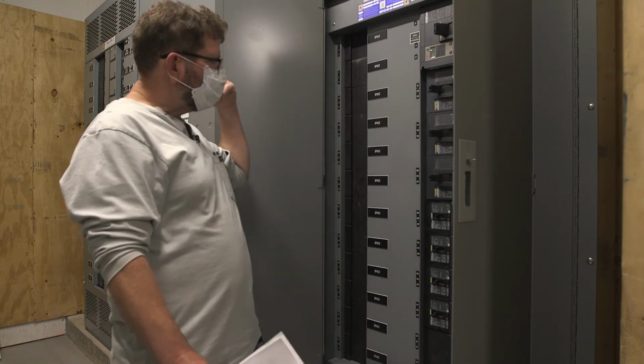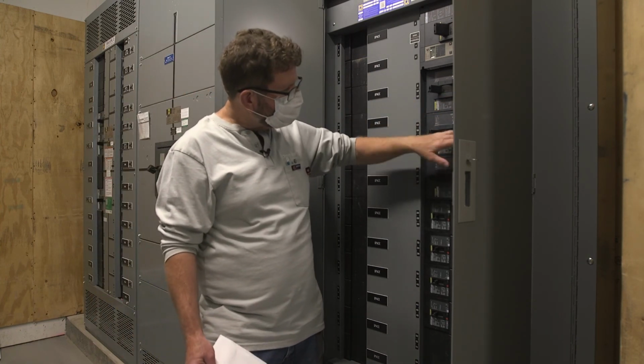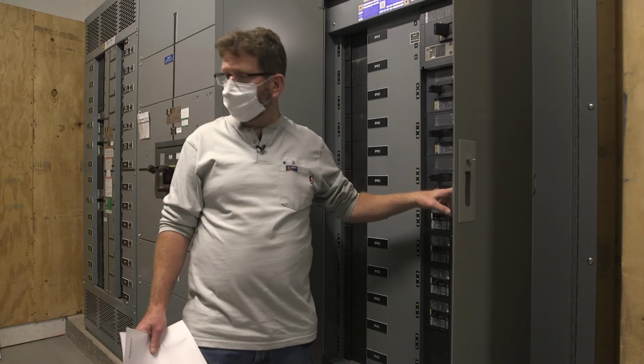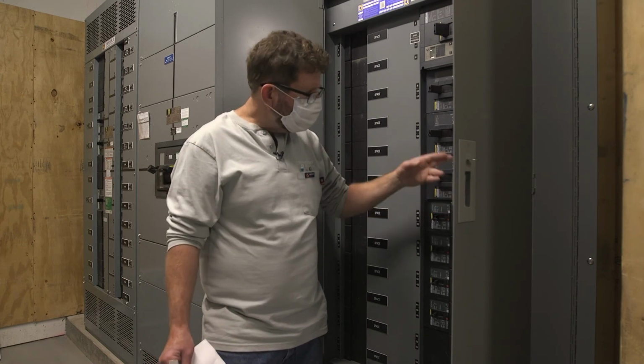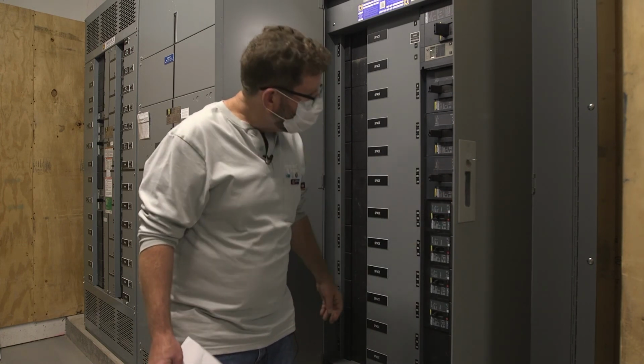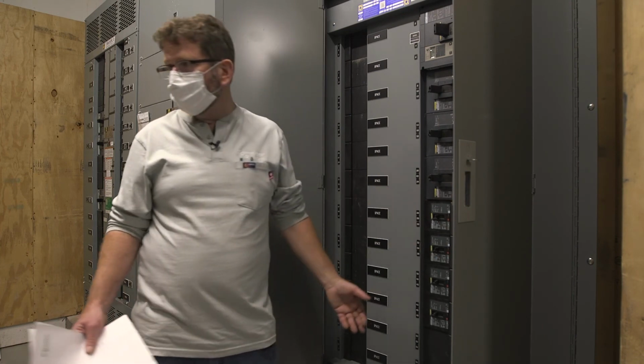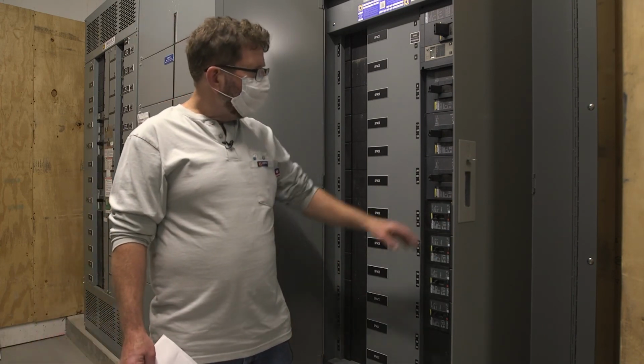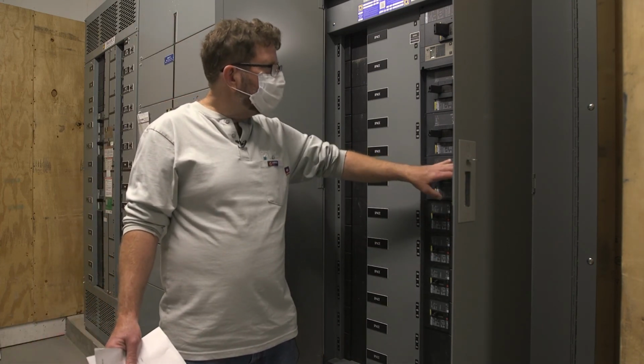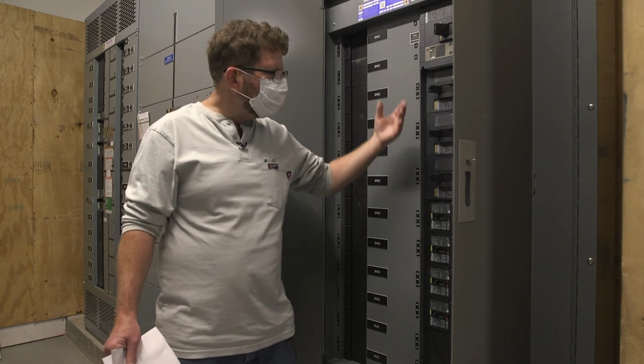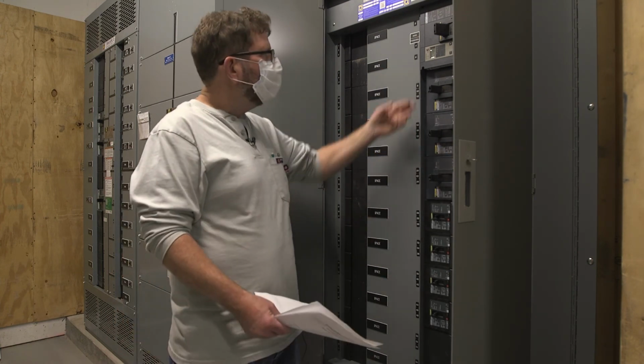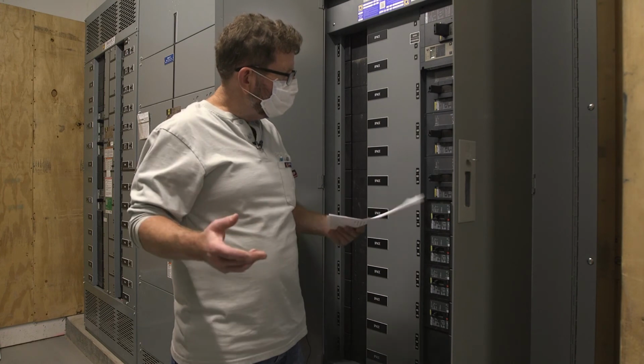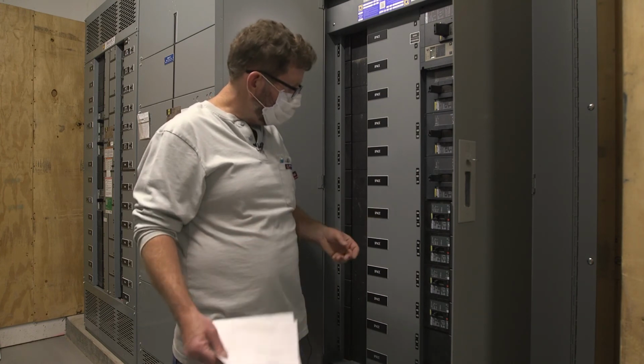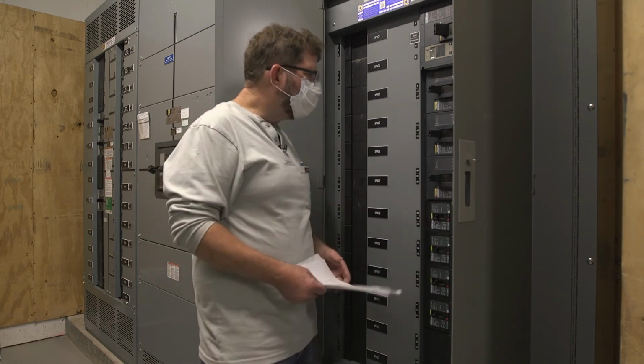These are just like those breakers. This is similar to these breakers, except it also has a display. And you're only going to see information on the display when you have enough load going through the breaker. There is an option to get control power into these. It would be a 24-volt control power. These displays would be lit up and active through the entire range, but that is just an option.